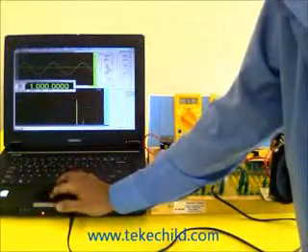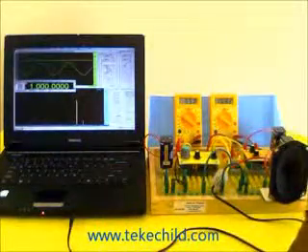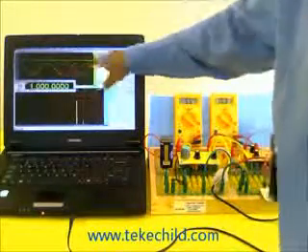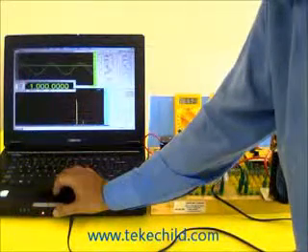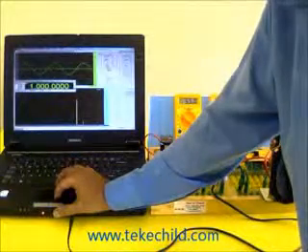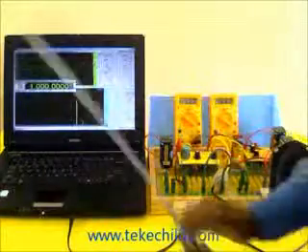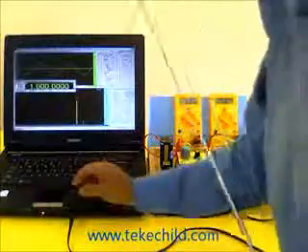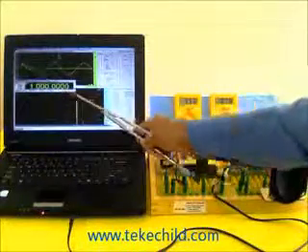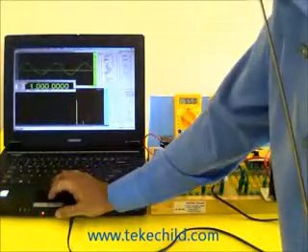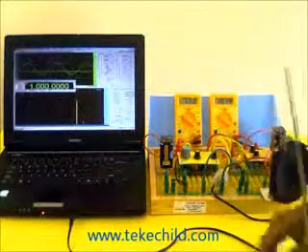This is the trigger. By triggering, the waveform becomes stable; if you don't trigger, the waveform will be moving. See — now it is not triggered and the trigger level is set higher than the amplitude of the wave, so the wave is not stable. Trigger it so it will stop. This level is called the trigger level; you can set it anywhere you like. You can trigger the wave from positive or negative side. The wave starts positive going negative, or starts negative going positive depending on your trigger selection. If you change the trigger level, it triggers from that level.